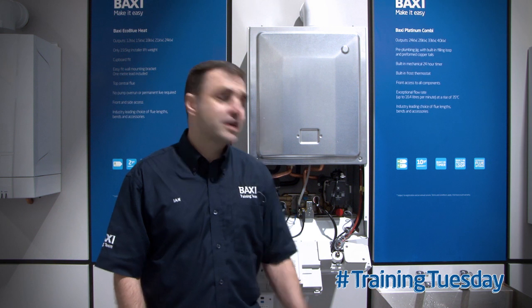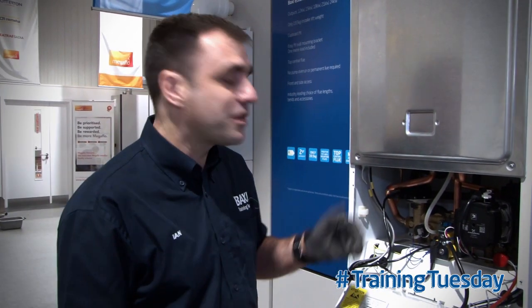Today we're going to talk about keeping the boiler cool while trying to commission the unit. If, when putting your Baxi Duo-tec or Platinum boiler into commissioning mode, the radiators are already hot, you may have trouble keeping the unit on and preventing it from overheating. This is a quick, easy way of stopping that from happening.